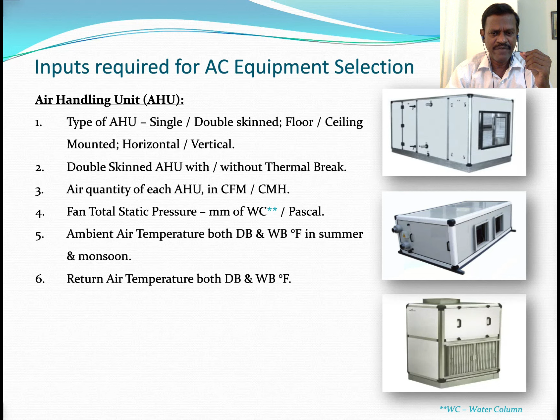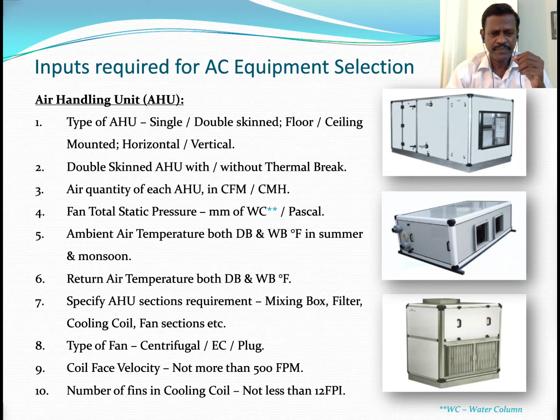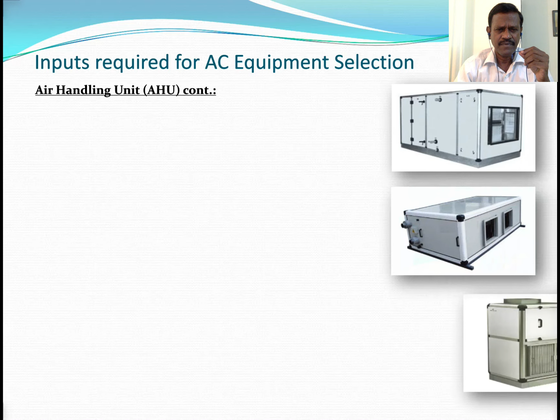Then type of fan, you have to mention whether you want centrifugal, forward curve or backward curve, EC fan or plug fan. And then coil face velocity you have to specify. It should not be more than 500 fpm. So coil selection should always be lesser than 500 fpm face velocity. And number of fins in the cooling coil not less than 12 fpi. Then coil size, whether you want a half inch coil or 5/8 inch coil.